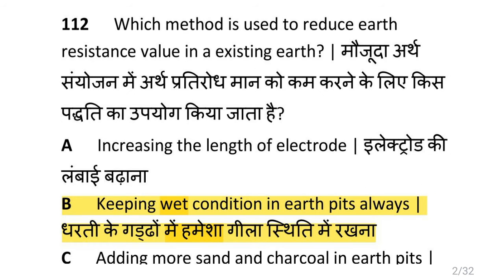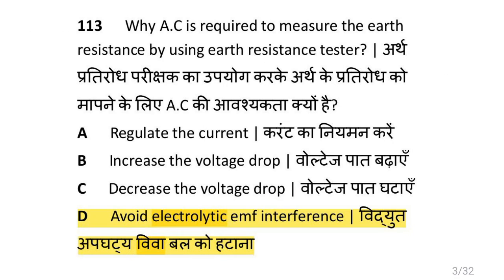Which method is used to reduce earth resistance value in an existing earth? That is keeping wet condition in earth pits always. Why is AC required to measure the earth resistance by using earth resistance tester? To avoid electrolytic EMF interference.